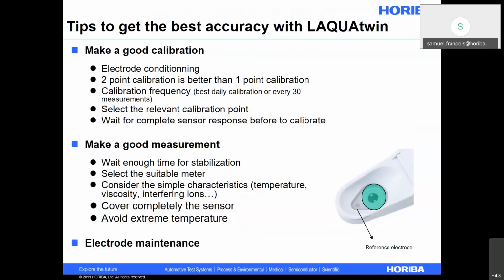So now there are some tricks to get the best accuracy with your LAQUAtwin meters. First, we want to make a good calibration. This is very critical. And before that, we want to do an electrode conditioning. Electrode conditioning is not always necessary, but it is very critical when the meter has not been used for a long time. When the meter has not been used for a long time, we need to put some solution to recondition the electrode. Otherwise, if we do the calibration directly, we will see the meter drifting as we do the measurement.